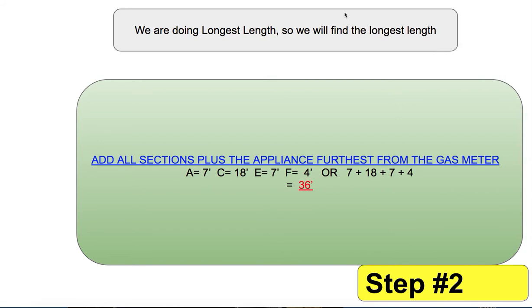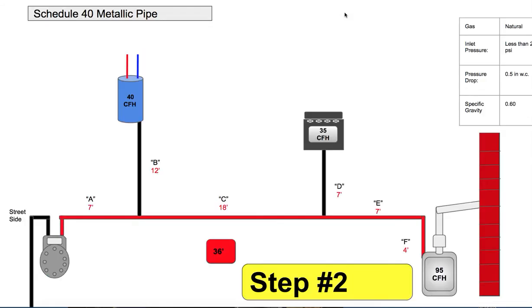Now, it's the longest length method, so we have to find the longest length — from the meter outlet to the furthest gas appliance. So in this example, you add up the main from the meter outlet to the furnace, because the furnace is the furthest gas appliance away from the meter. You get 36 feet — sections A plus C plus E plus F equals 36 feet.